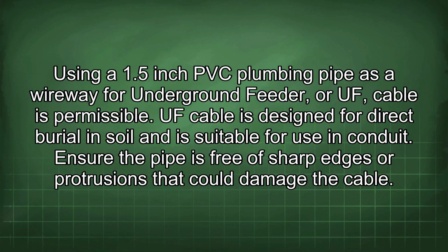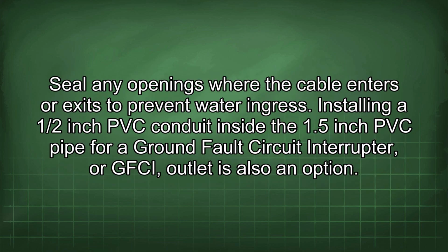Using a 1.5-inch PVC plumbing pipe as a wireway for underground feeder, or UF, cable is permissible. UF cable is designed for direct burial in soil and is suitable for use in conduit. Ensure the pipe is free of sharp edges or protrusions that could damage the cable. Seal any openings where the cable enters or exits to prevent water ingress.